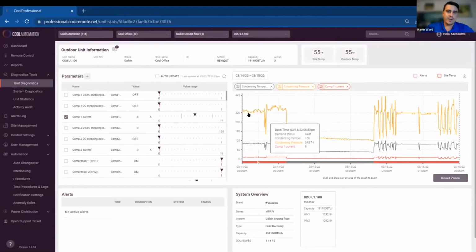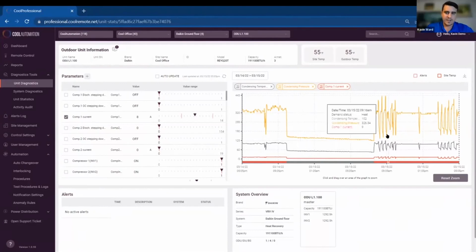So all of the operating pressures, temperatures, and in this case, we even have the compressor current. You can see that when the system is off, your current is 0, but as the system starts to engage in the heating cycle, now we're seeing some actual compressor current, as well as the increased condensing pressures and temperatures. So having visibility of each of these diagnostic points allows us to create specific anomaly rules that are actively monitoring each of these points for you.